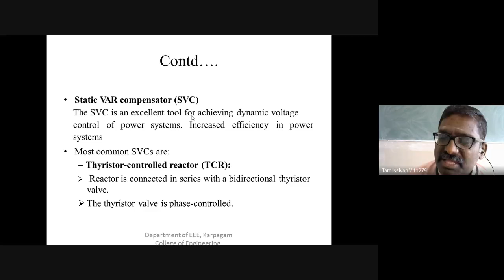The most commonly used SVC is the thyristor controlled reactor, where the reactor is connected in series with the bidirectional thyristor valve. The thyristor gate is controlled by the phase control method. It may also be a thyristor switched reactor, called TSR, which operates in either zero or full conduction mode, but its equivalent reactance varies in a stepwise manner.